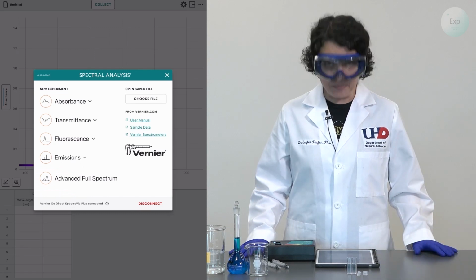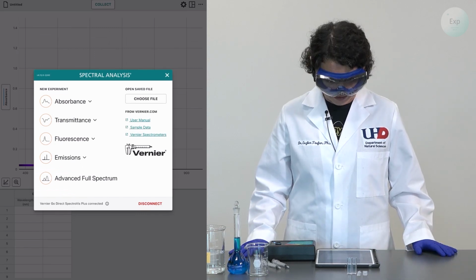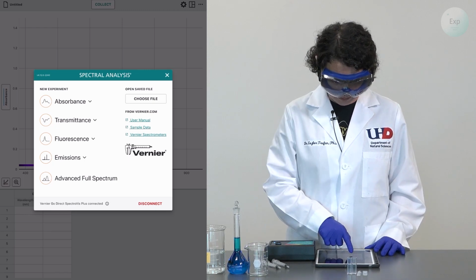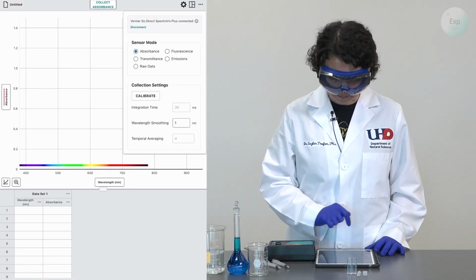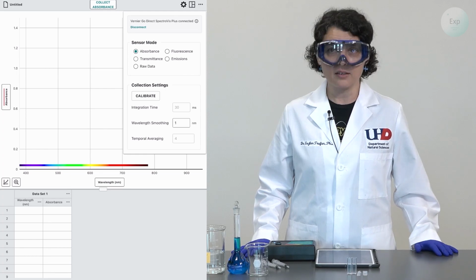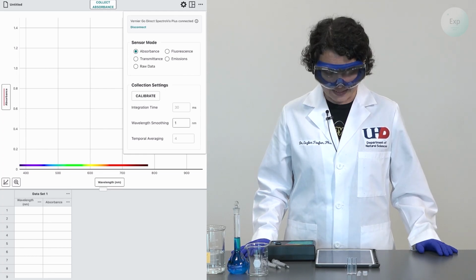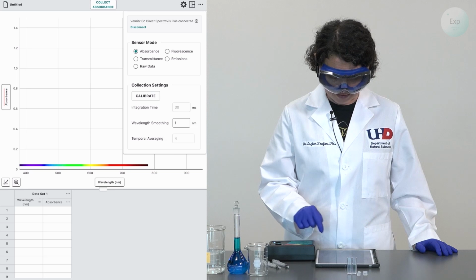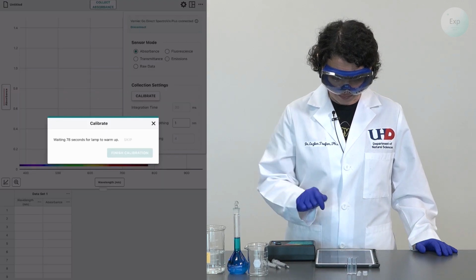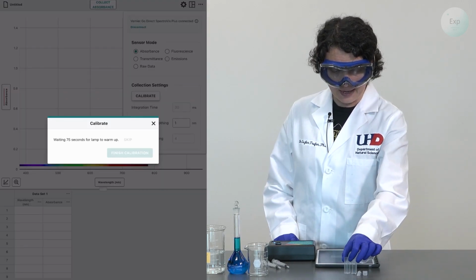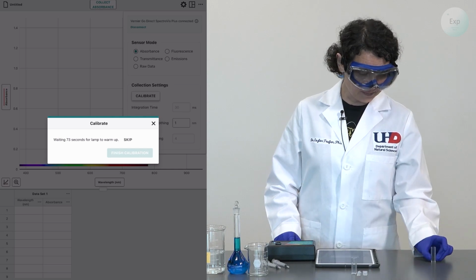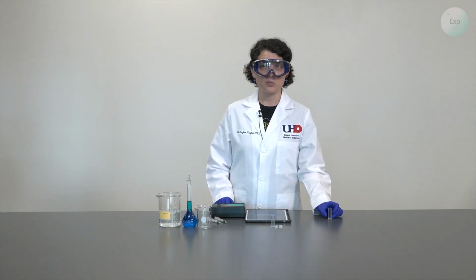Once the connection is established, we will need to calibrate our instrument. And to do that, we're going to press Advanced Full Spectrum. We need to place our sensor in the appropriate mode today. We will be focusing on absorbance. So I highlighted absorbance, and we press the Calibrate button.